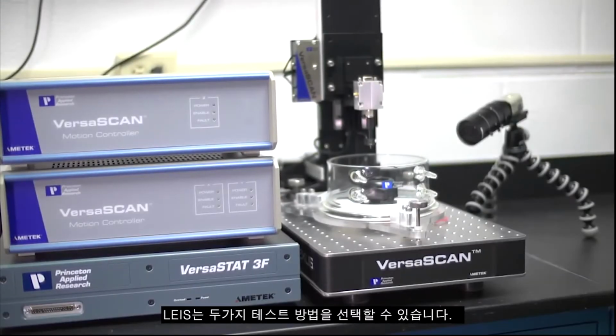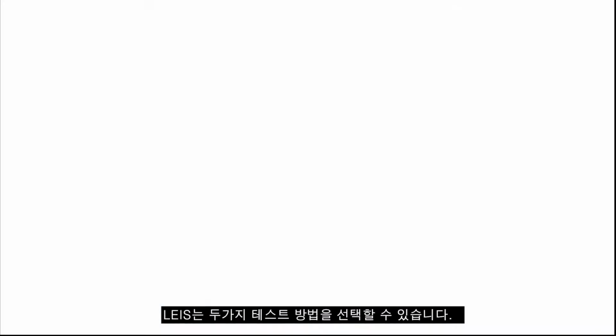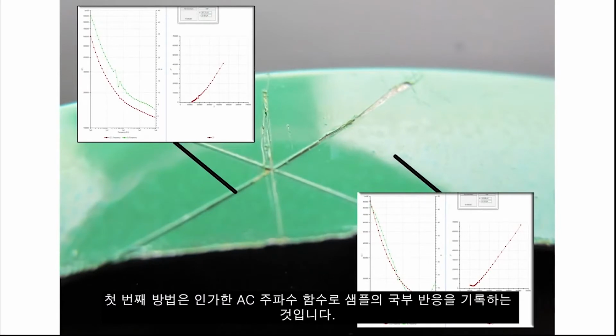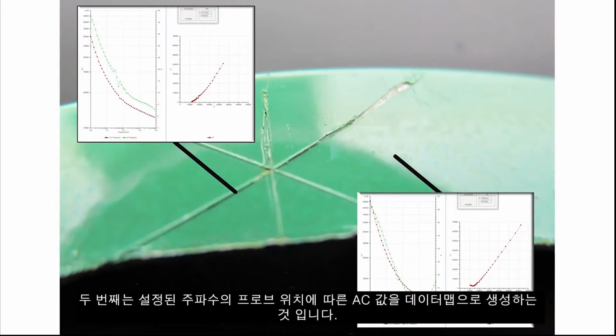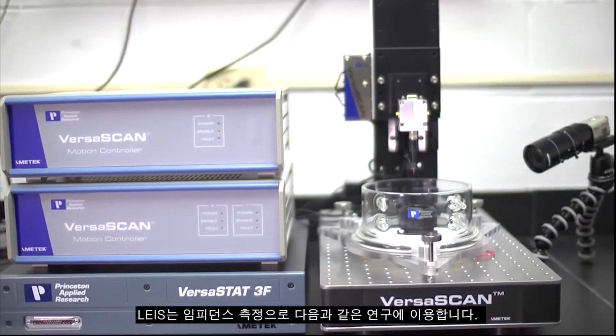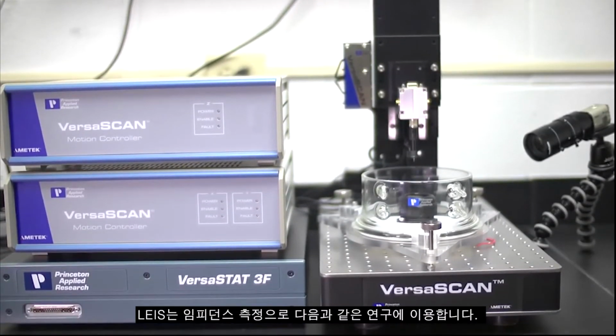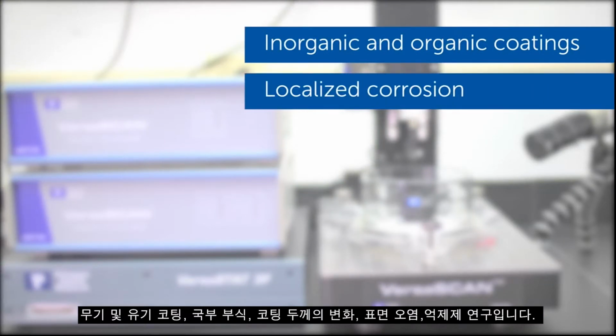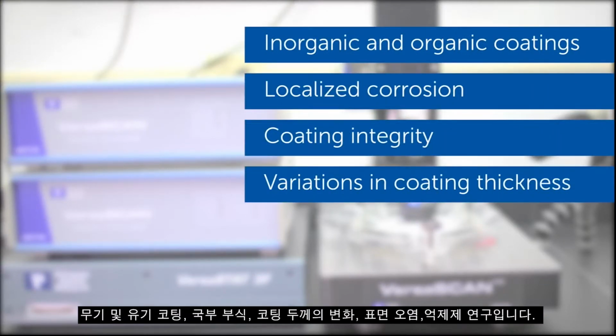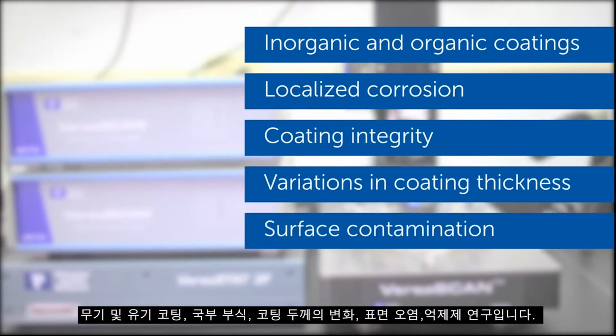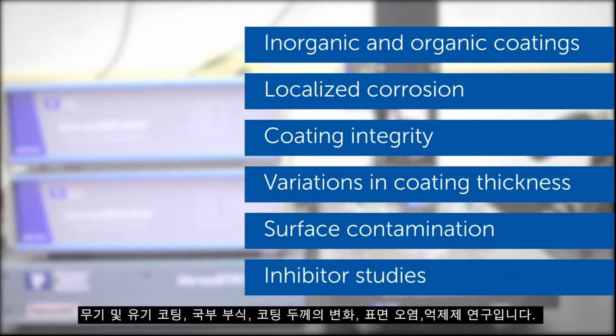There are two LEIS test methods for the researcher to choose from. The first method entails the charting of the local response of a sample as a function of applied AC frequency. The second allows the user to create a data map to characterize an AC response as a function of probe position at a set frequency. LEIS provides a spatially resolved impedance measurement that adds value to the research of inorganic and organic coatings, localized corrosion, coating integrity, variations in coating thickness, surface contamination, and inhibitor studies.